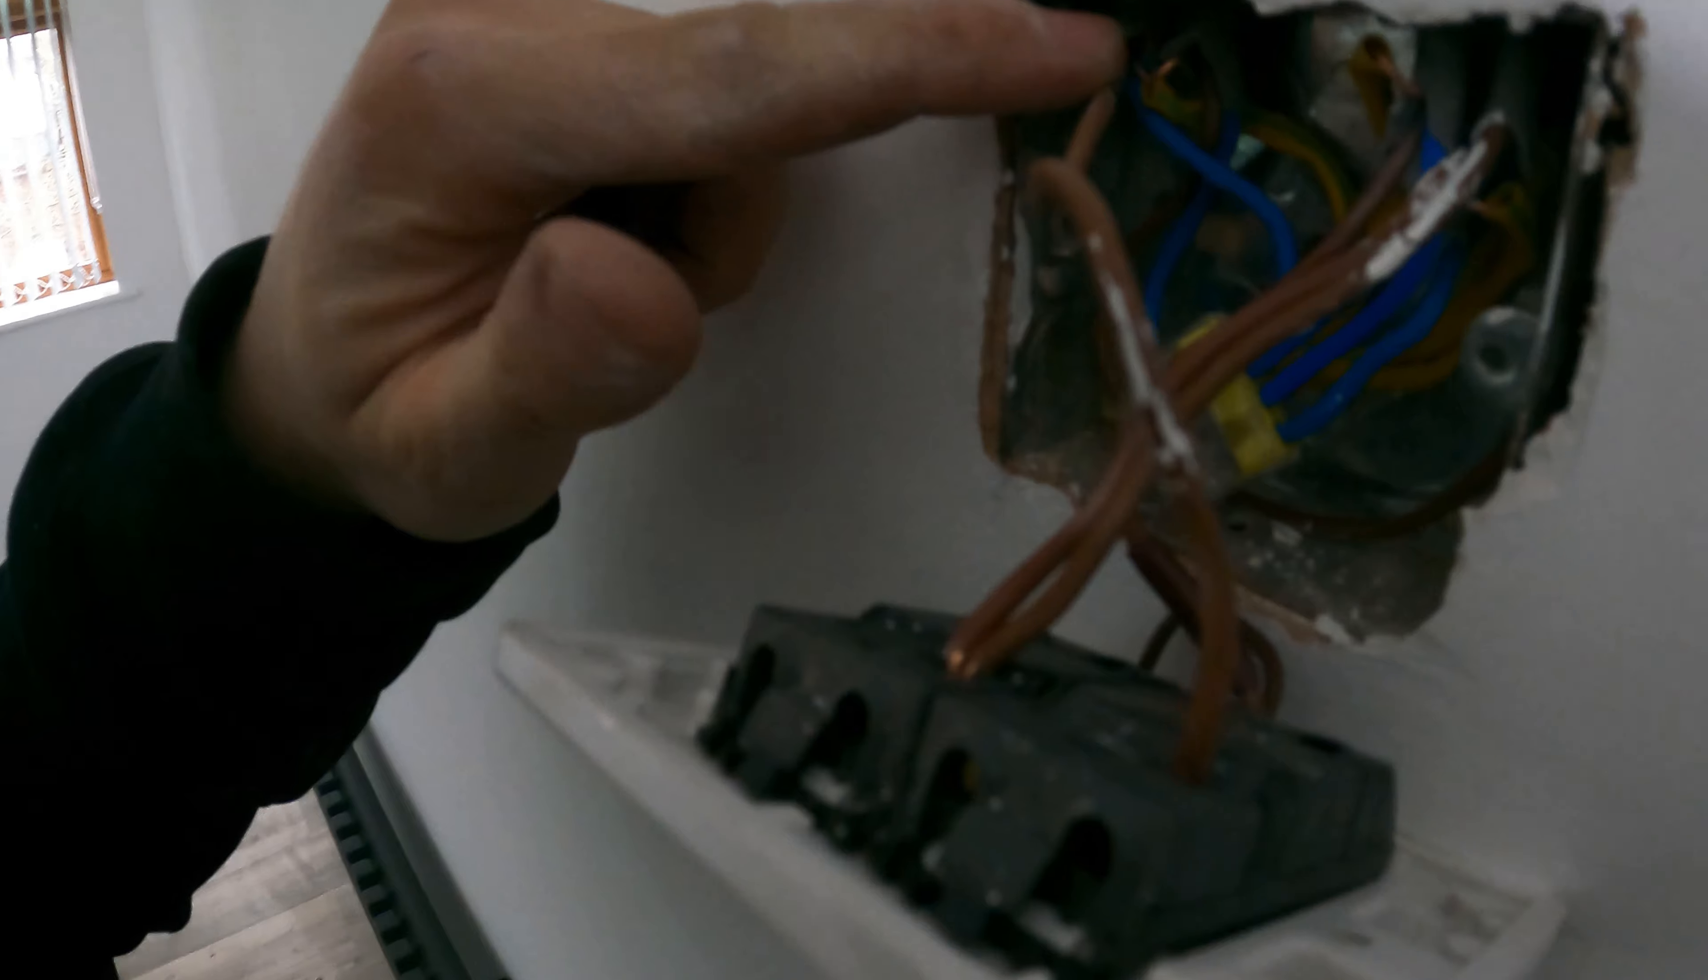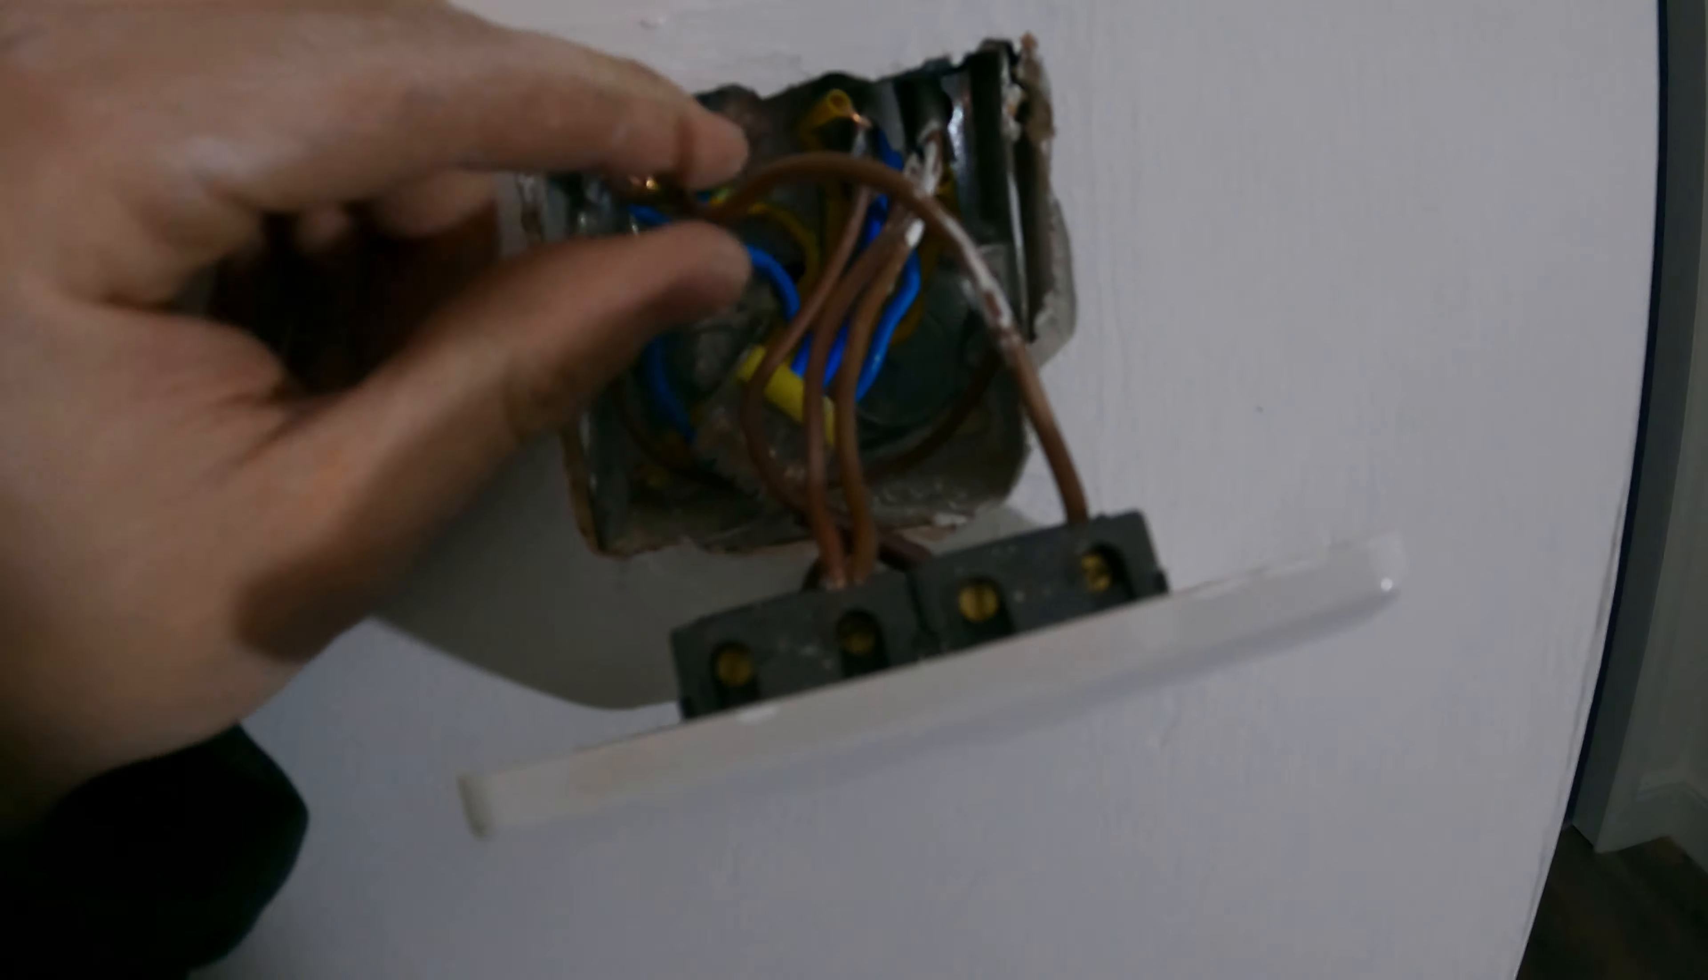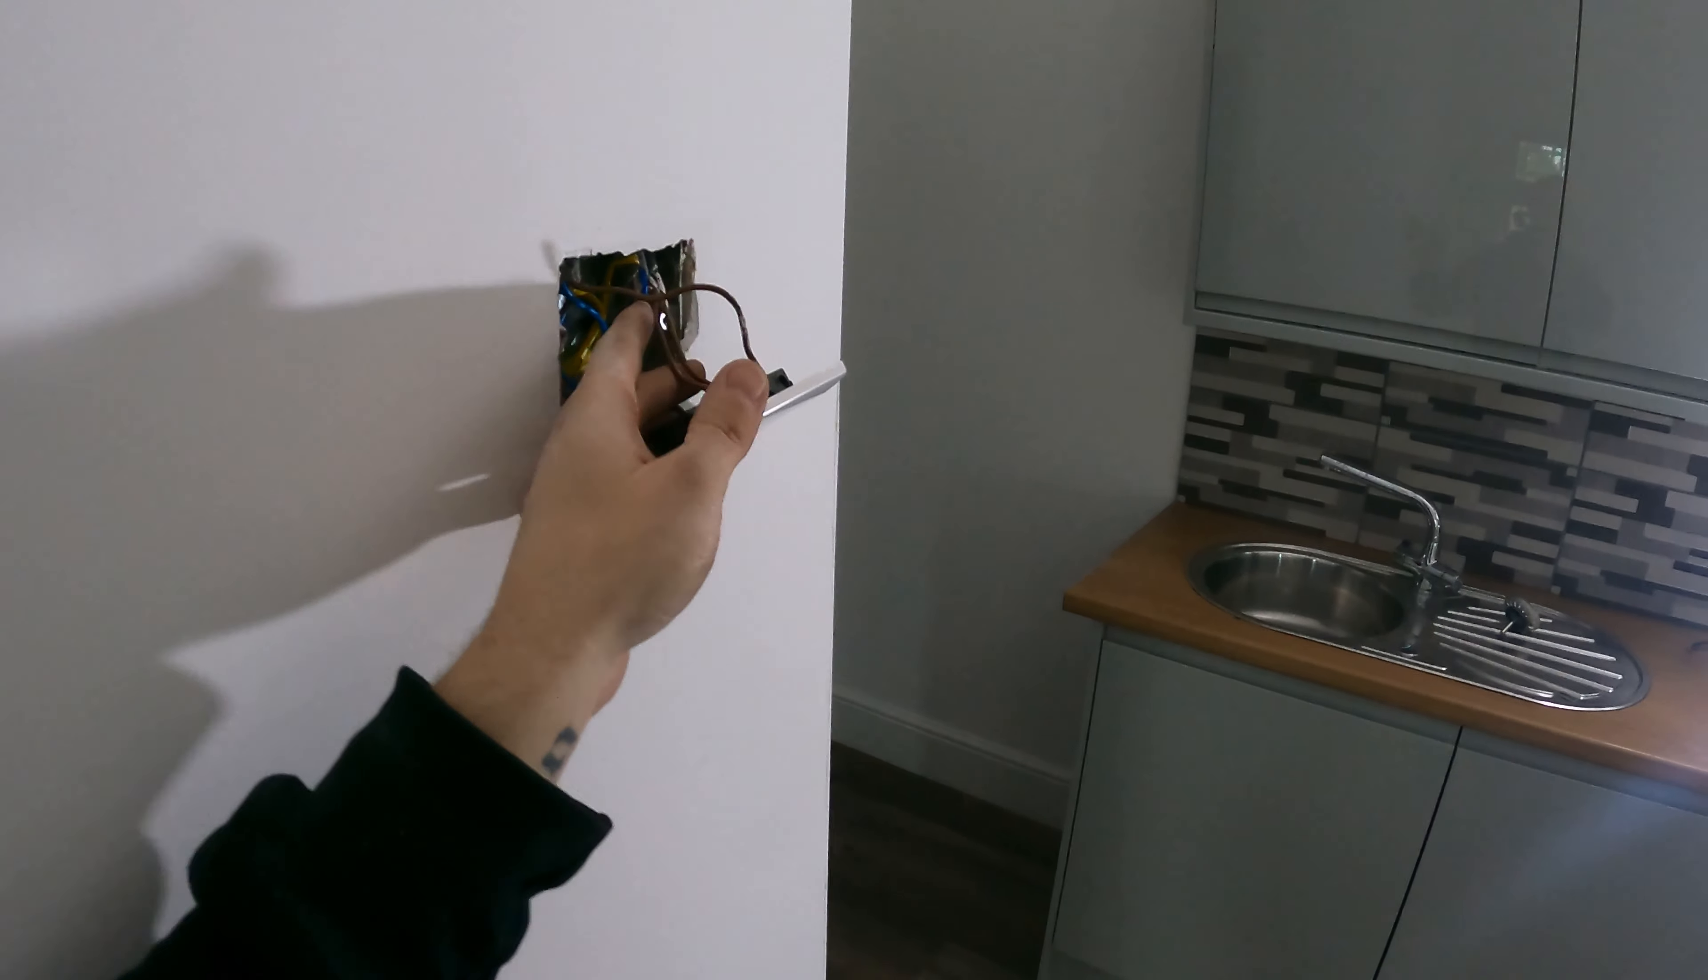Then we've got a switch wire going out to the under cabinet lights, the little pyramid ones under there. That other one there, that's not connected to anything. And there's the neutral cut. That's the ring that he had going over there to them lights. And then he's got these two switch wires that switch these lights. So I'm assuming what he would have done is gone up and gone to that light, gone to that light, gone to that light, came back down to the switch and just connected up like a ring for no apparent reason.